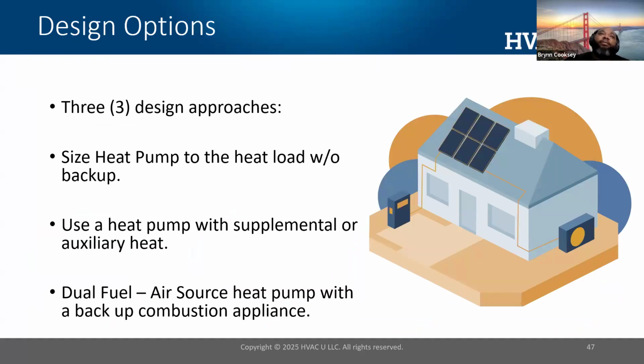Now, when you're designing heat pumps, there are three design approaches that you could take. The first design approach is to size the heat pump to the heating load without backup. Remember, heat pumps can deliver all or nearly all of their capacity at very low temperatures. The technology is amazing. The second way is to use a heat pump, but have some type of supplemental or auxiliary heat, where the heat pump makes up a large portion of the heating load, but I use a supplement like electric resistance heat to make up the difference.